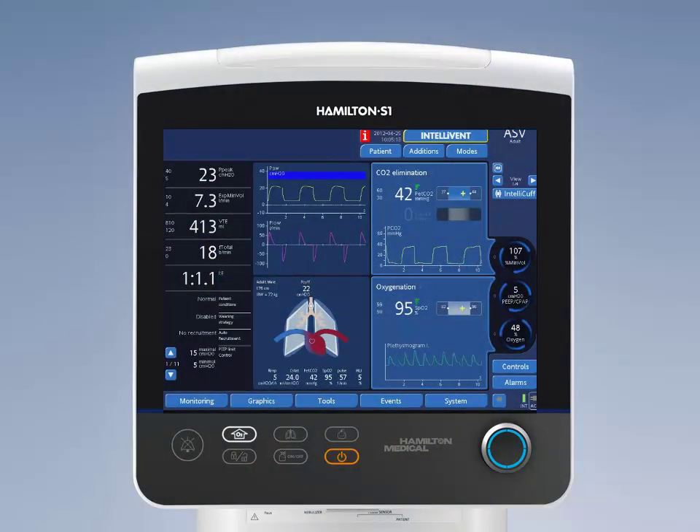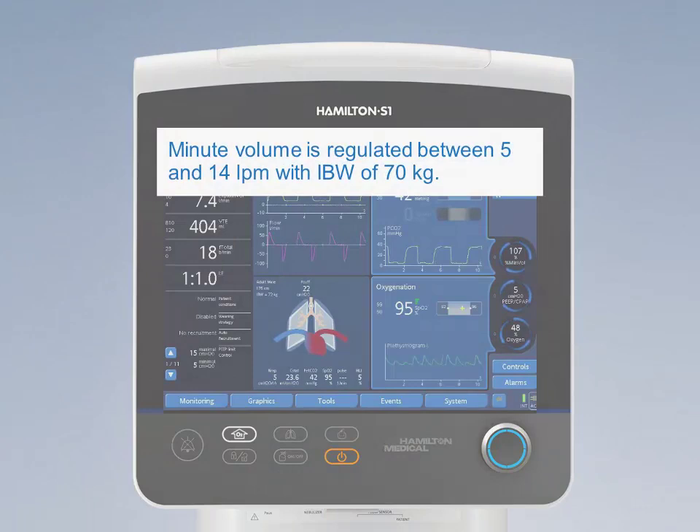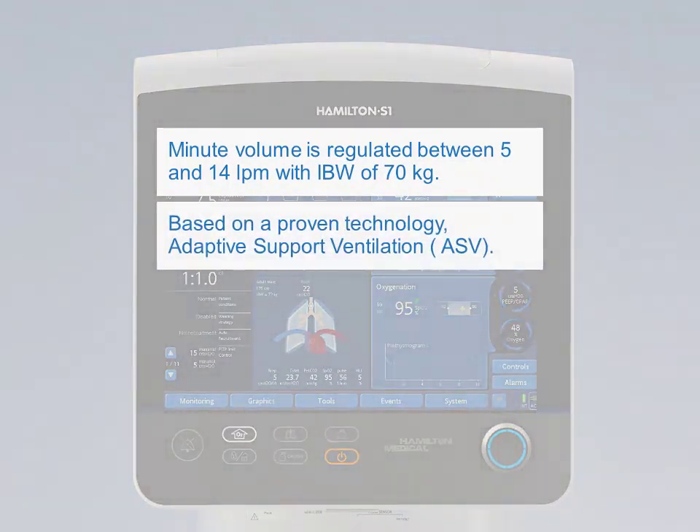How safe is IntelliVent ASV? IntelliVent ASV is very safe. Automation of minute volume ensures end-tidal CO2 will be maintained within safe ranges set by the physician. Minute volume is regulated between 5 and 14 lpm with an IBW of 70 kg. Hamilton Medical's proven technology — adaptive support ventilation (ASV) — is the basis of IntelliVent ASV, using the safe window to visualize the limitation of VT, Pmax alarm, and RR based on the expiratory time constant of a specific patient.